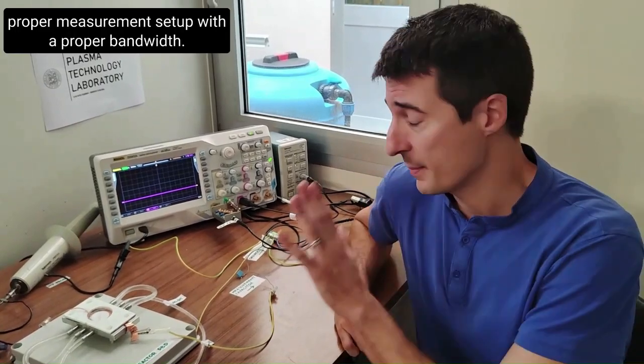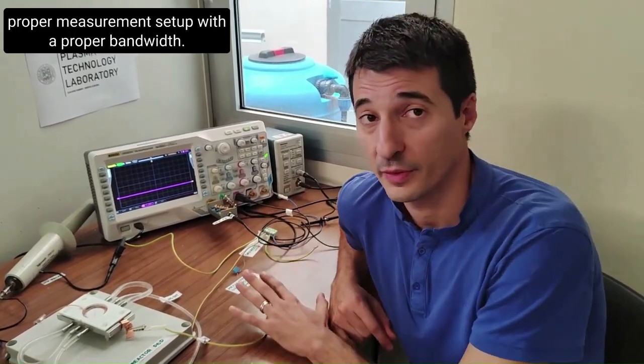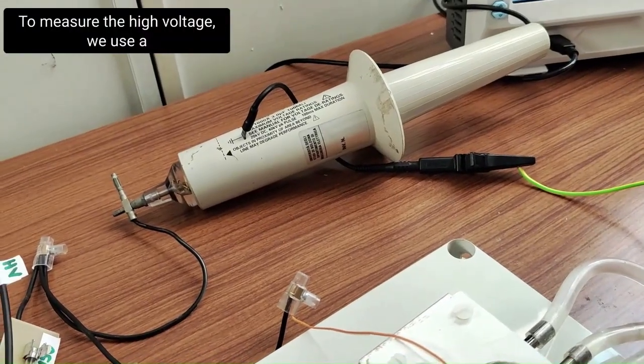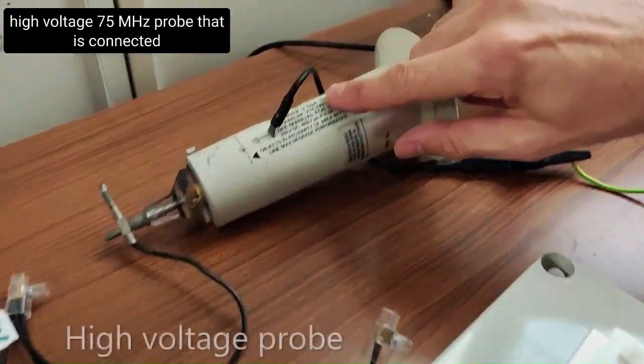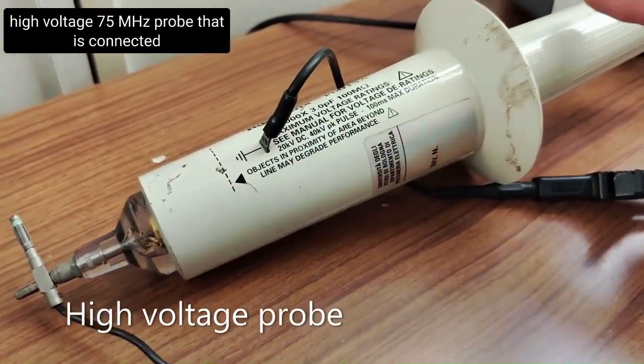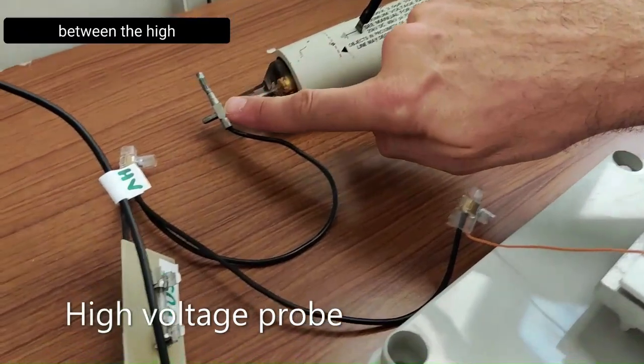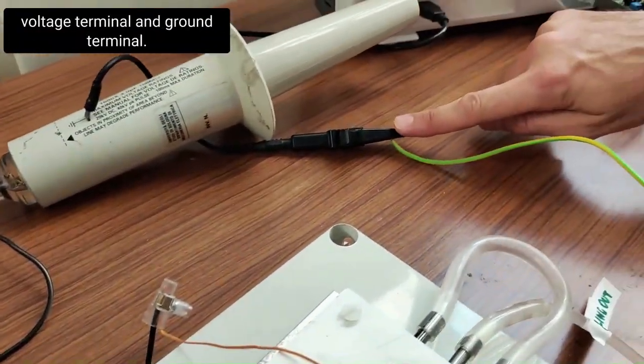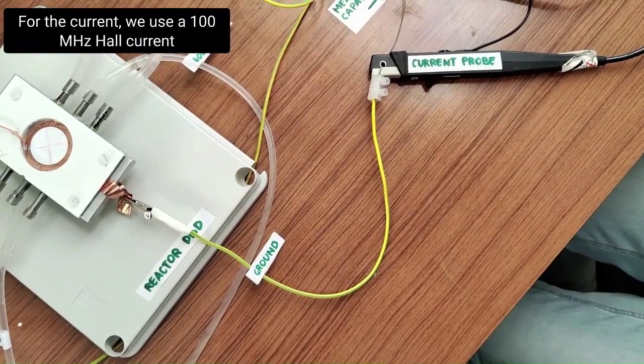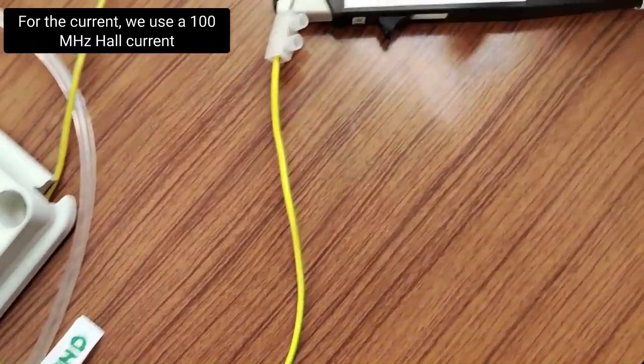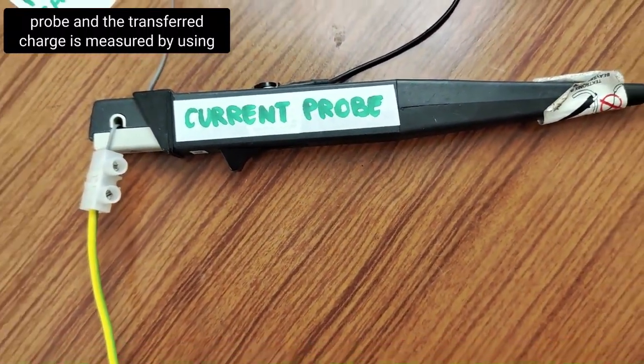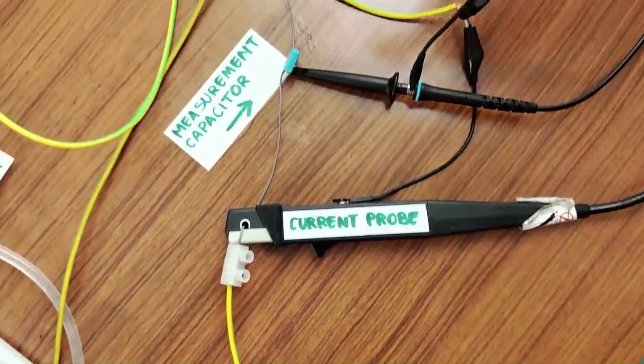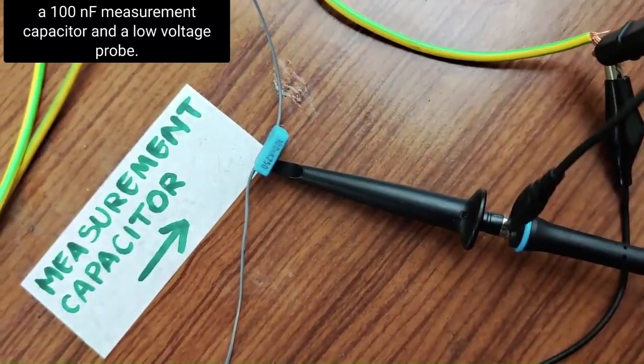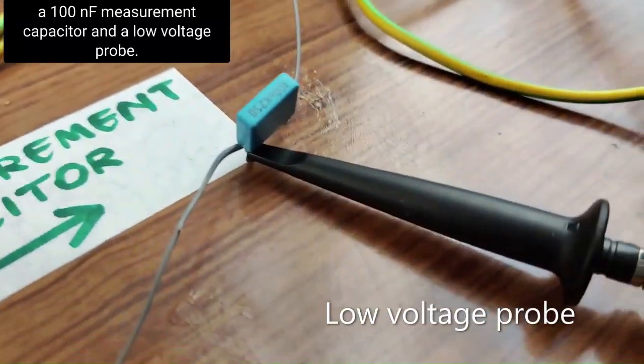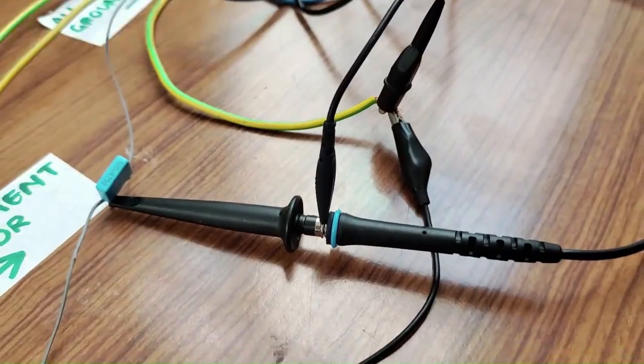For this reason you need a proper measurement setup with proper bandwidth. To measure the high voltage we use a high voltage 75 MHz probe connected between the high voltage terminal and ground terminal. For the current, we use a 100 MHz hall current probe, and the transferred charge is measured using a 100 nanofarad measurement capacitor and a low voltage probe.